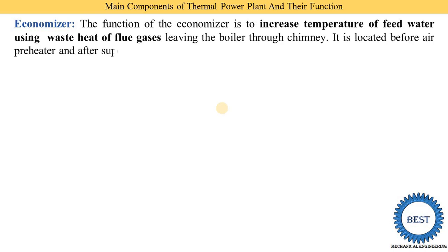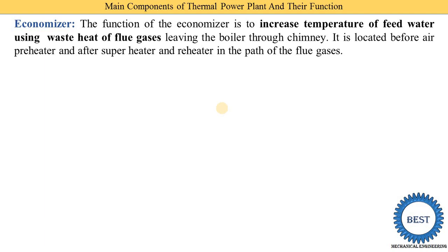The function of the economizer is to increase the temperature of feed water using the waste heat of the flue gas leaving the boiler through the chimney. The water is first supplied to the economizer, where its temperature is increased, and then this high-temperature water is supplied to the boiler. The economizer is installed before the boiler — first water enters the economizer, temperature is increased, and then it is supplied to the boiler.